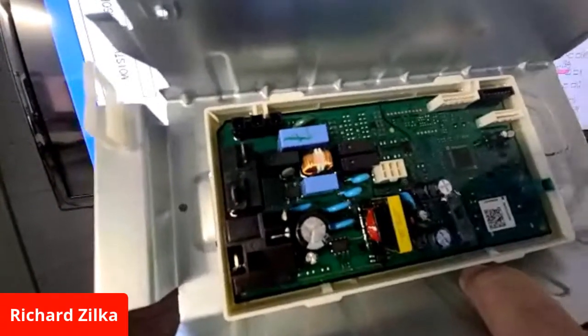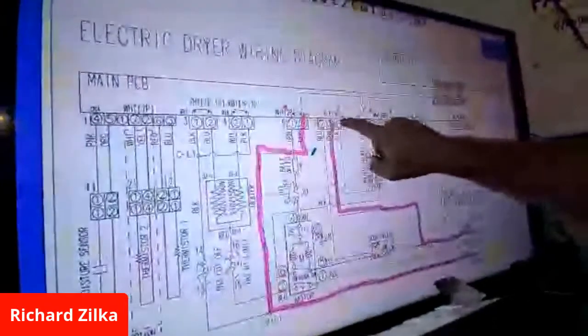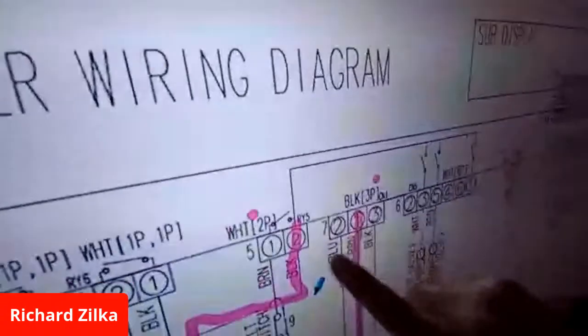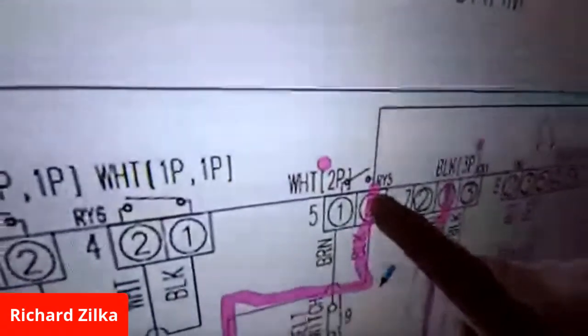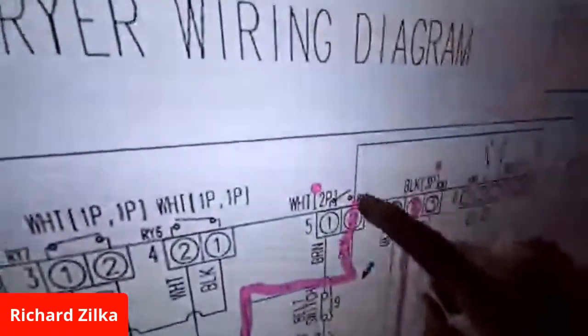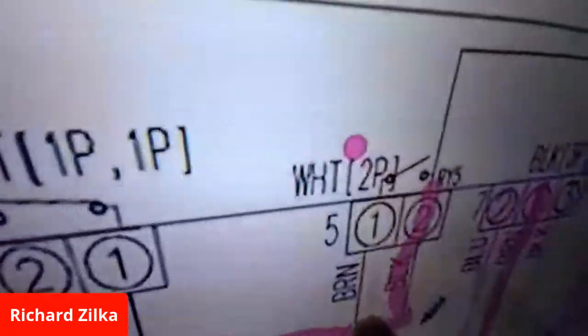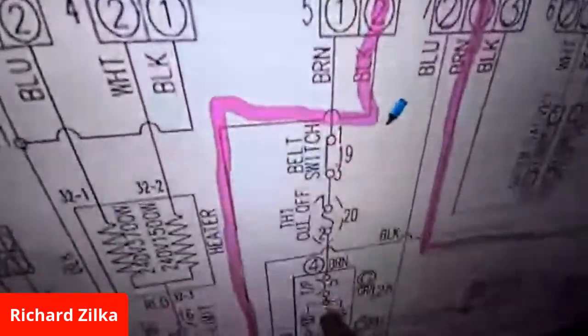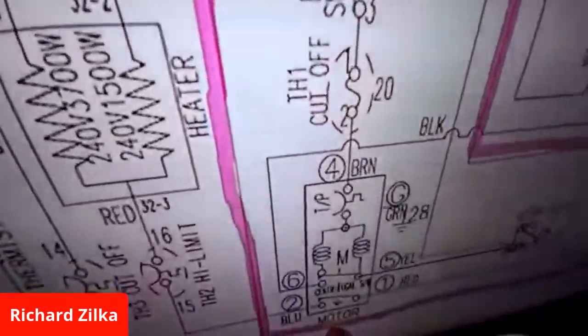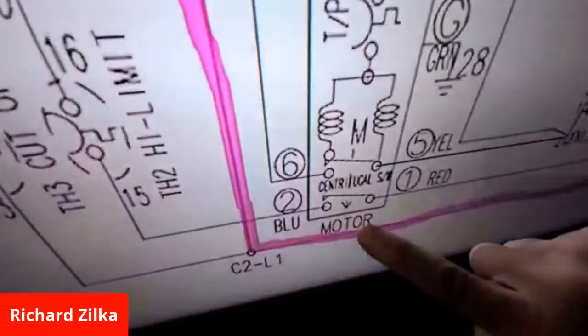We're going to look for this brown wire here on connector number 1, and we're going to look for this black wire here on relay number 5. Relay number 5 is also the motor relay. Following it down here, it goes to the motor where the centrifugal switch is, and down here it says motor. So that is one of these relays here.